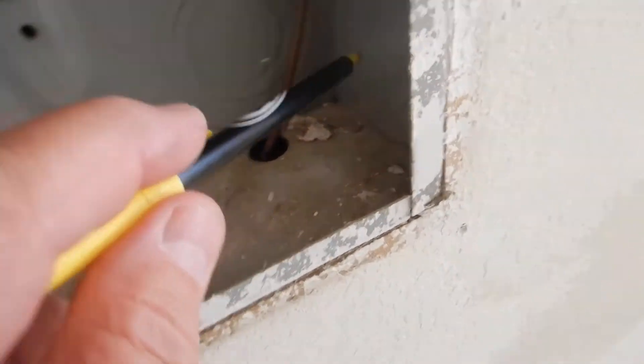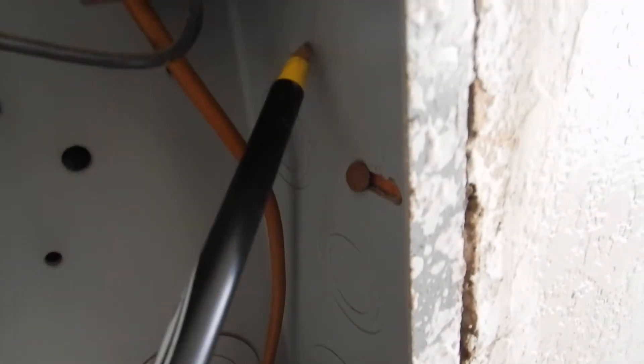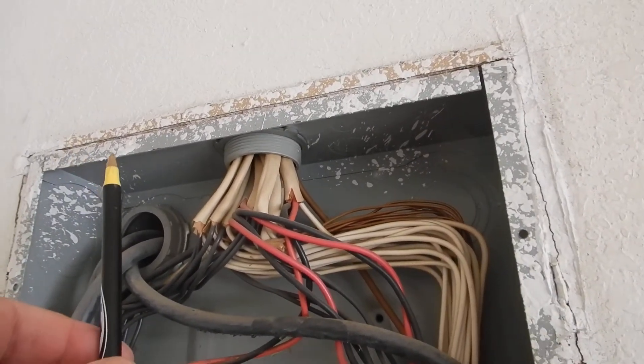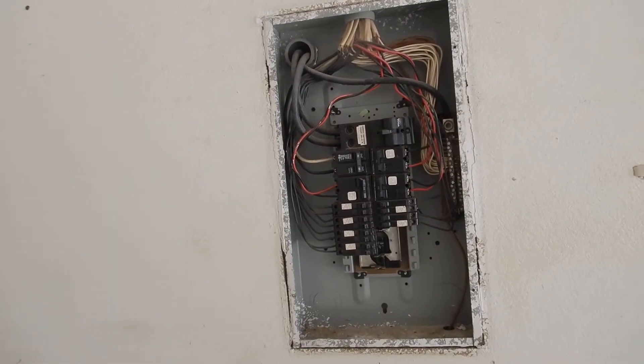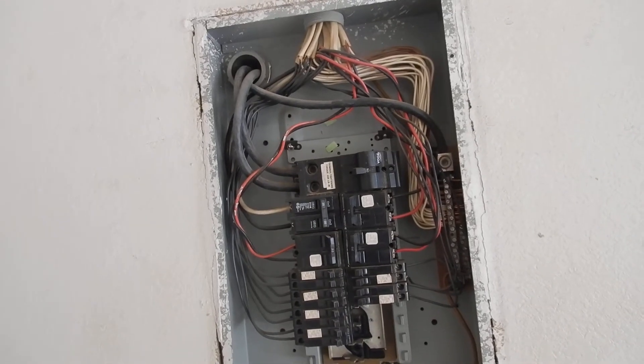Let's talk about bundling. This is for L1 and L2, so it fits in almost every house. You can see these smaller knockouts — these are for these wires. My illustration baked into the report is somewhat apologetic, and I hate apologizing for my work. But bundling is very common. You could knock all these out, bring them in, take all the sheetrock out and do all the work, but it's not going to change the selling value of the house. It would be a little safer, but in relative terms, not much.